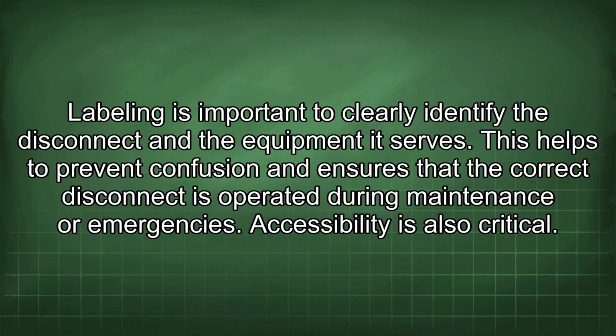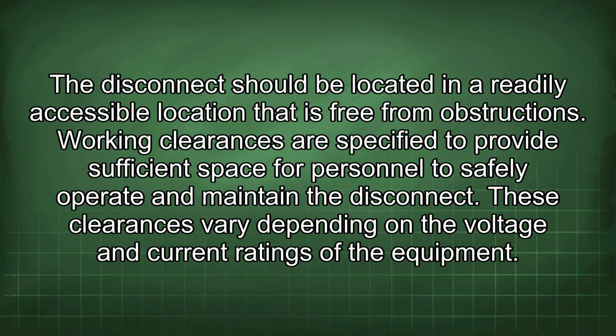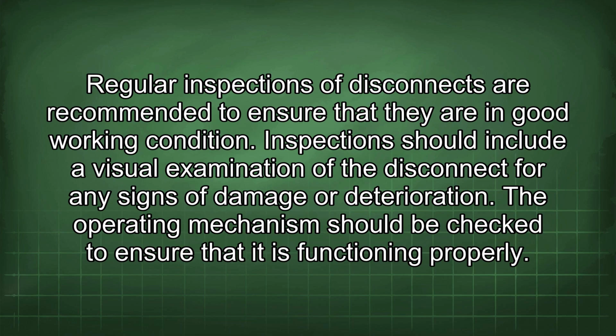Accessibility is also critical. The disconnect should be located in a readily accessible location that is free from obstructions. Working clearances are specified to provide sufficient space for personnel to safely operate and maintain the disconnect. These clearances vary depending on the voltage and current ratings of the equipment. Regular inspections of disconnects are recommended to ensure that they are in good working condition.